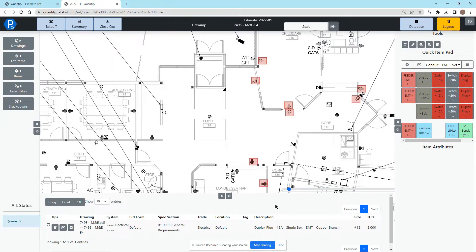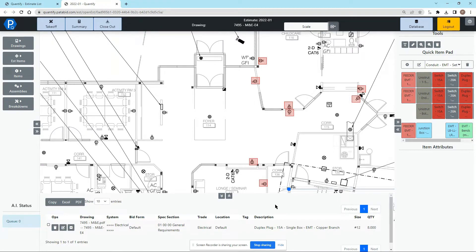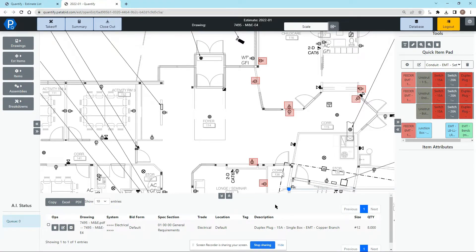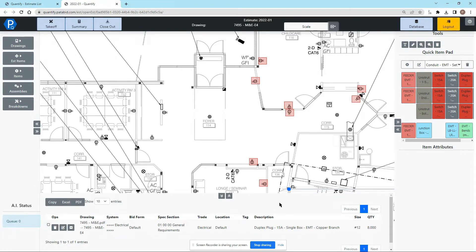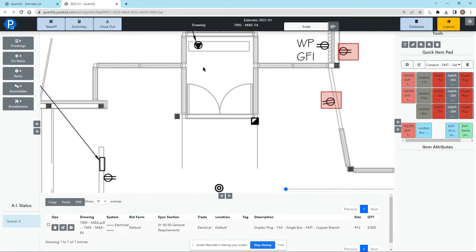Now let's run some cable and to do that we're first going to have to set a scale. Now the scale in Quantify is always set from a known dimension. This is because a PDF drawing could be altered without you knowing it and when you load it up you might not actually be working on the scale you think you are or the scale the drawing says it has on it. So we use a known dimension.